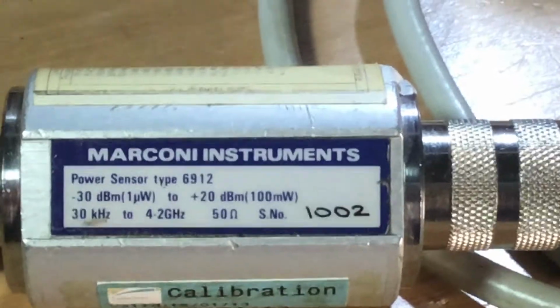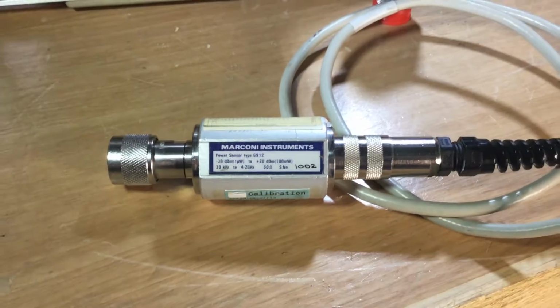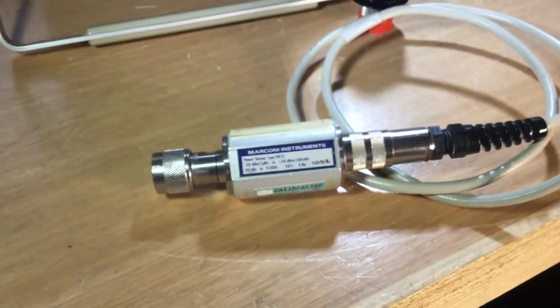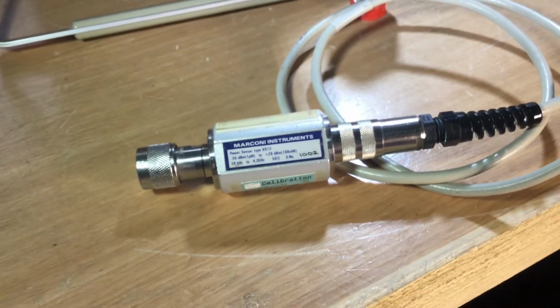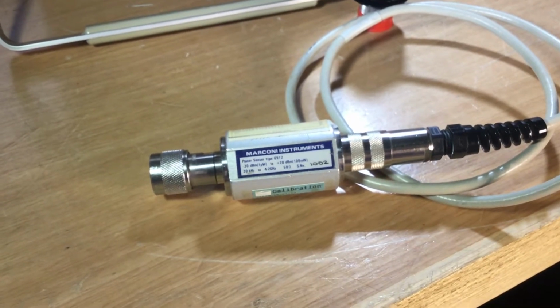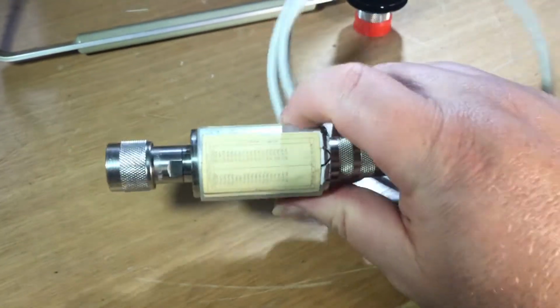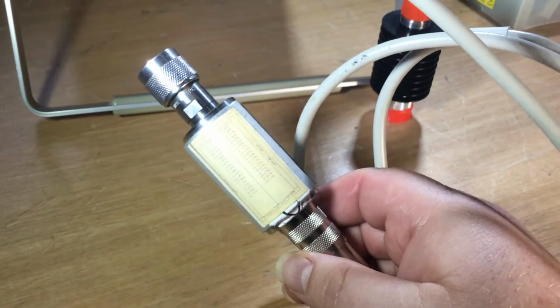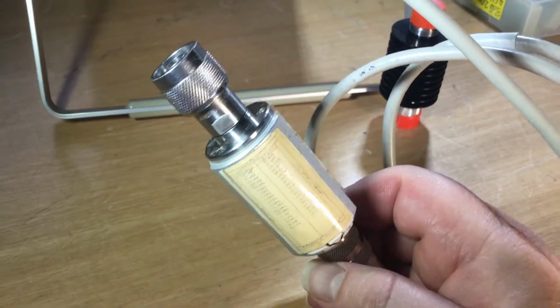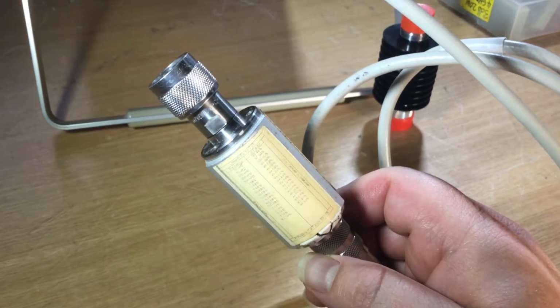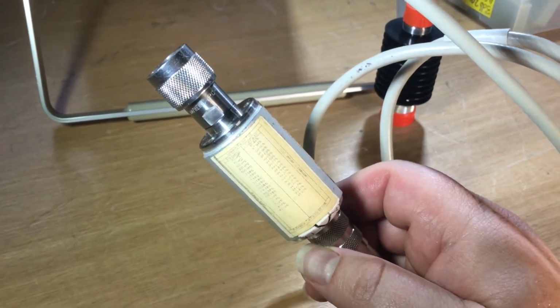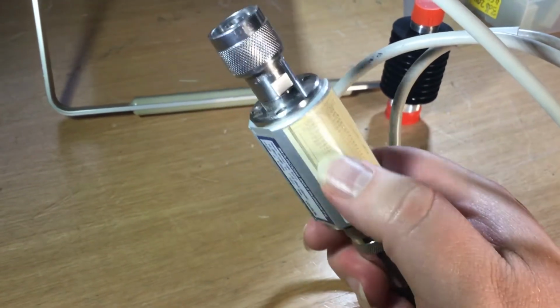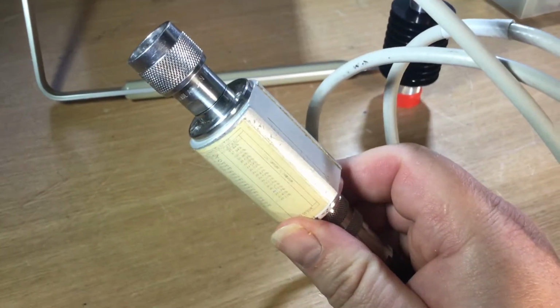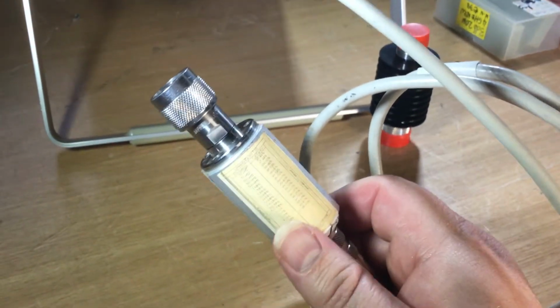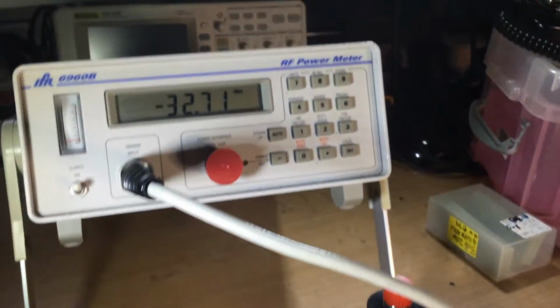So the other sensors give data as to how much RF power they could take in a pulsed application as well, which can be hundreds of times higher for a pulsed signal as opposed to a CW signal. Likewise as well, there's a chart on the other side which gives information about the linearity, calibration factor, duty cycle, etc. on the different frequencies throughout its frequency range is written on this table, and that's quite important data, because what we can do, we enter that in here.